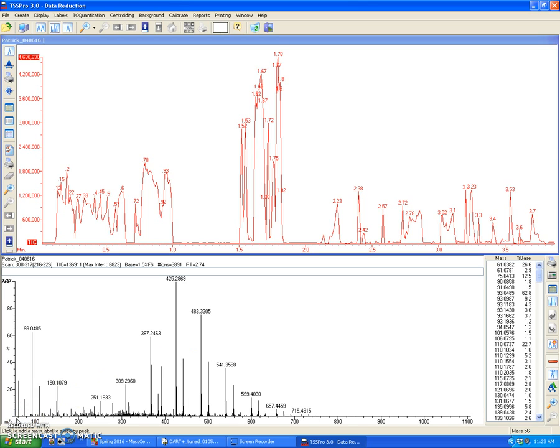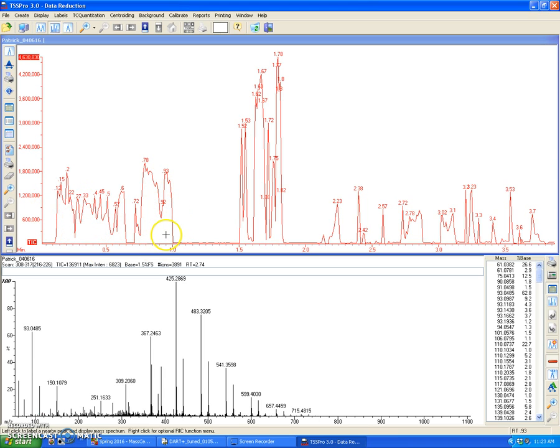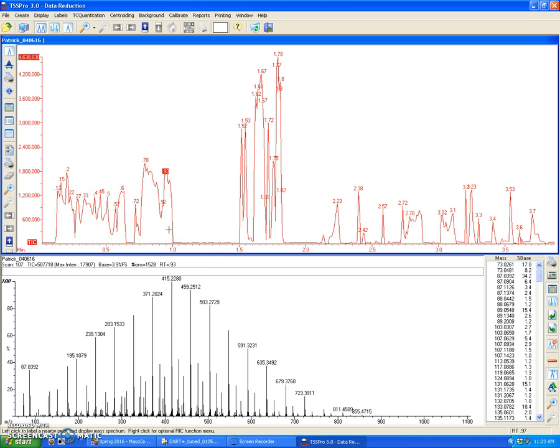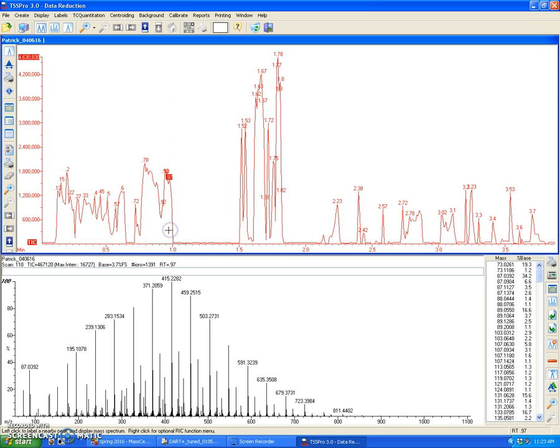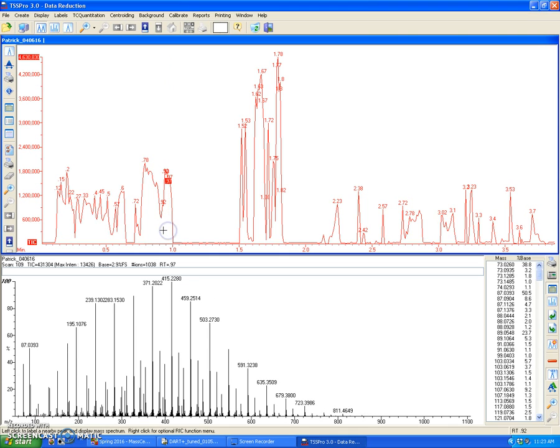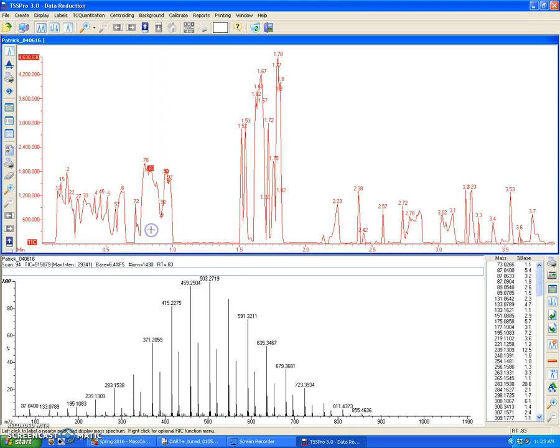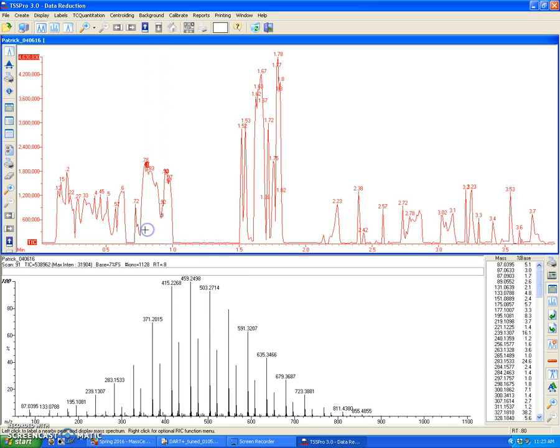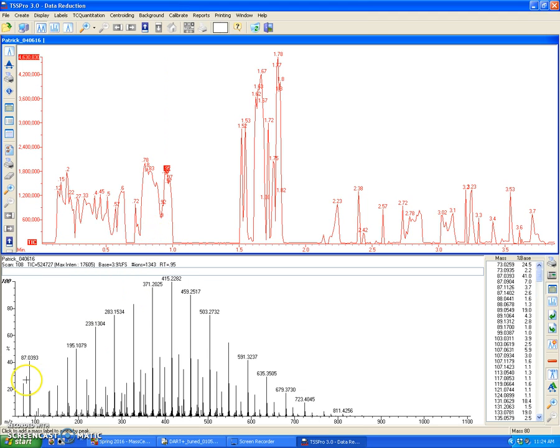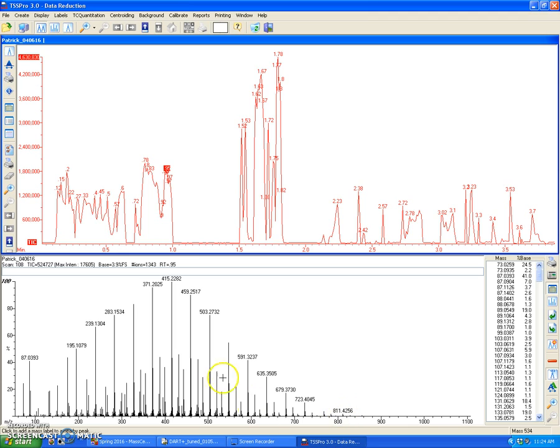The next thing that I'm going to do before I view any mass spectra for print or for publication is to calibrate it against the polyethylene glycol mass spectrum. So this region right here was where I acquired polyethylene glycol. And if I just click on a region, you can see the single mass spectra over time. And what I'm looking for is focusing on the polyethylene glycol region to where it focuses primarily where my analytes are.